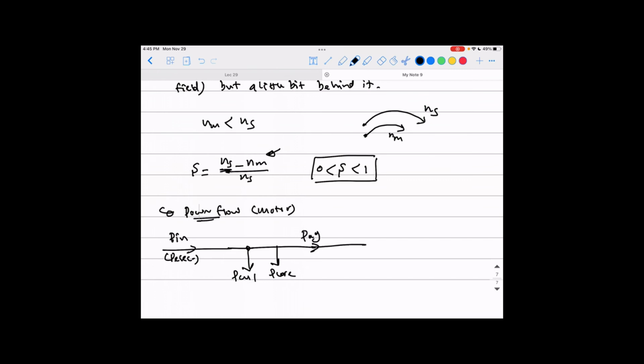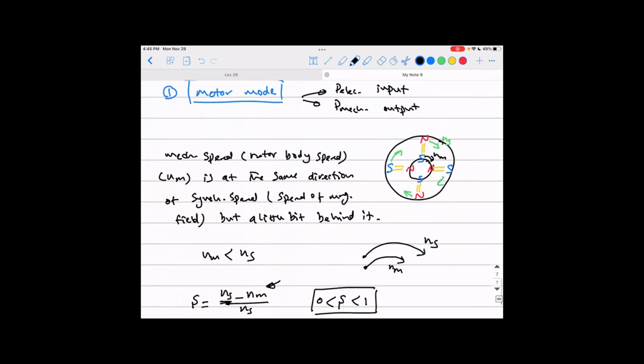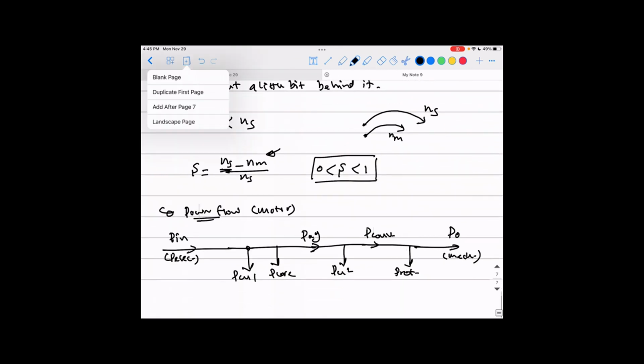The rest is your air gap power, the power that crosses the air gap from stator to rotor, and then you lose some as copper losses in the rotor. The rest is your converted power, lose some of it as rotational losses or friction windage losses or mechanical losses, whatever you want to call it, they are all the same. And the rest is your P output, which is mechanical power. Okay guys, that is the motor mode, which is all the time we dealt with before, so we should be good with this.